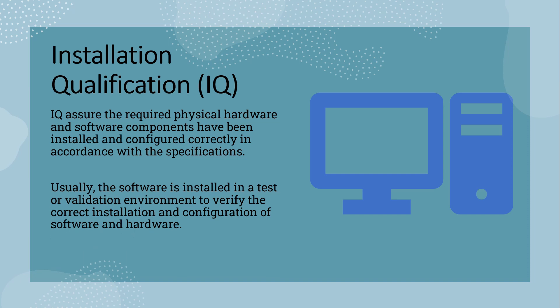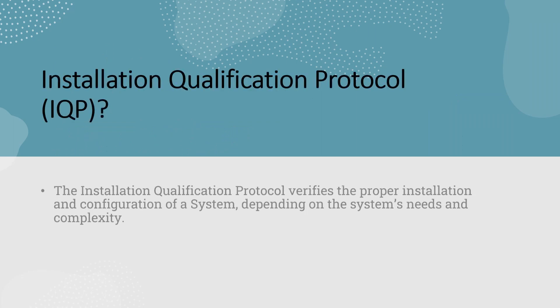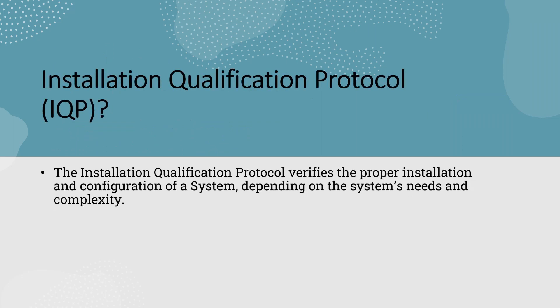Usually the software is installed in a test or validation environment to verify the correct installation and configuration of software and hardware. So now what is the installation qualification protocol? The installation qualification protocol verifies the proper installation and configuration of the system depending on the system needs and complexity. For installation qualification, we need to prepare a protocol which has a set of test scripts to verify the installation and configuration of the system.